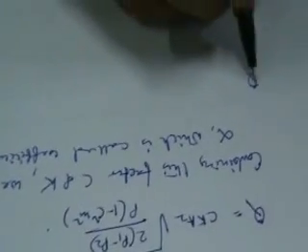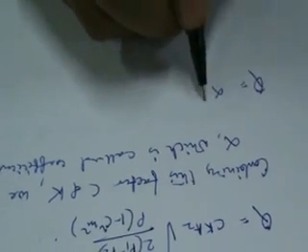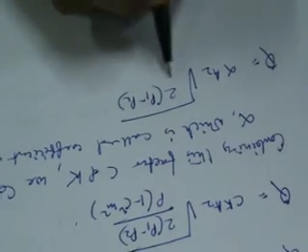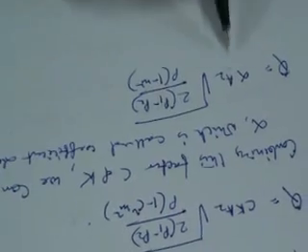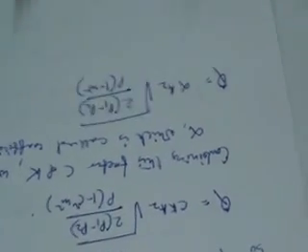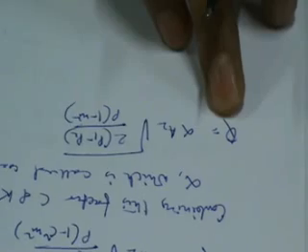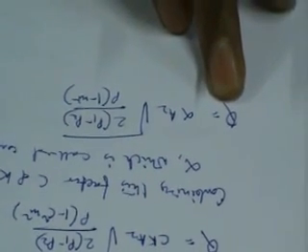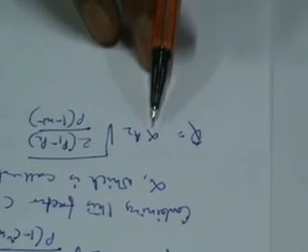The Q then becomes Q equals alpha A2 root over 2 (P1 minus P2) by rho times (1 minus m square). So if somebody knows the coefficient of discharge, and then measures the delta P across this orifice plate, obviously he will be able to find out the quantity flowing through the duct or pipe.